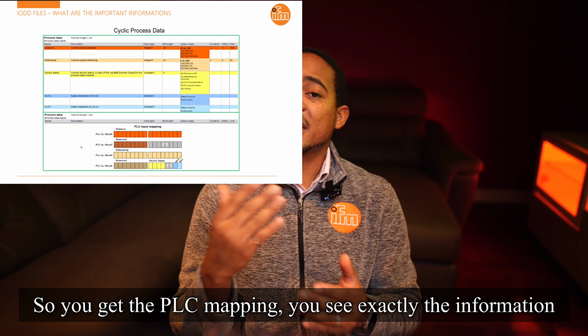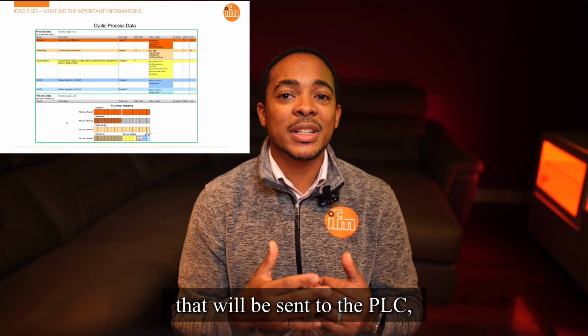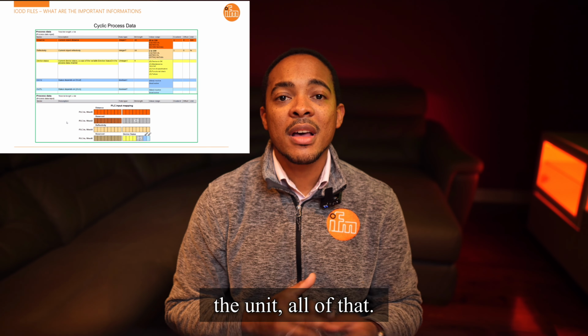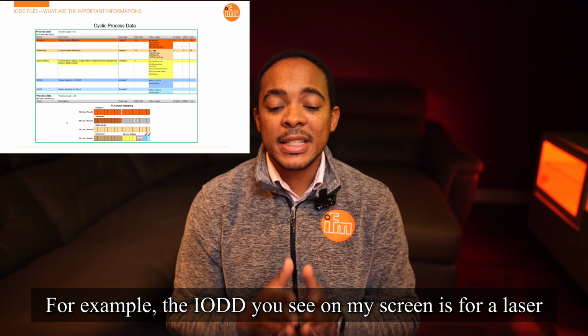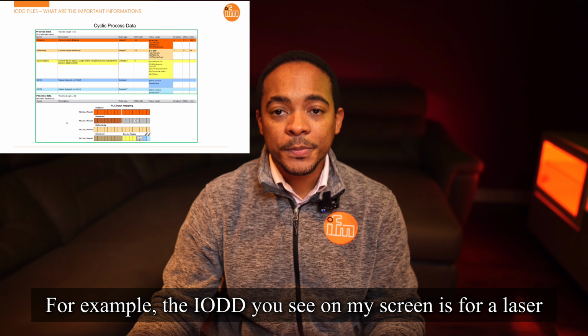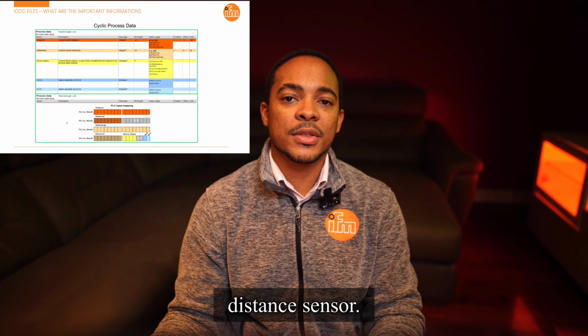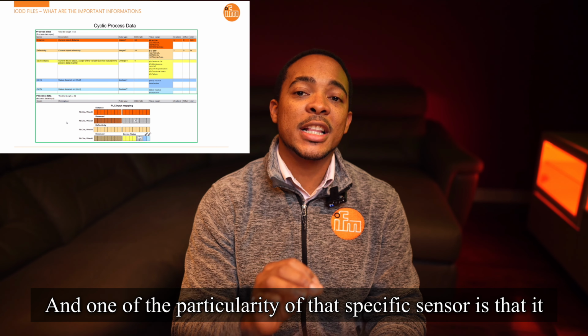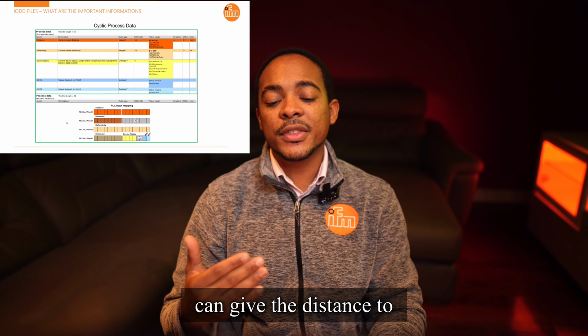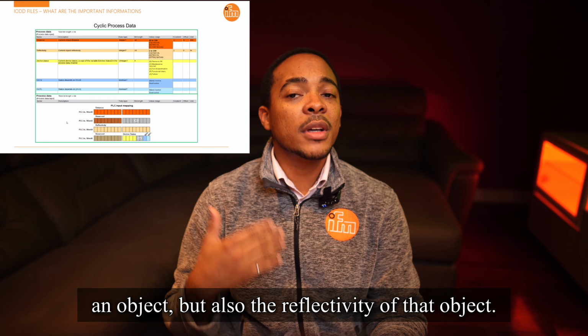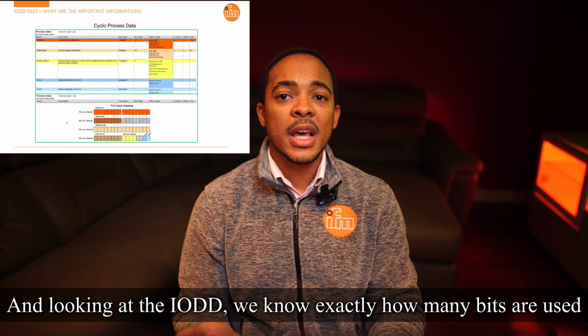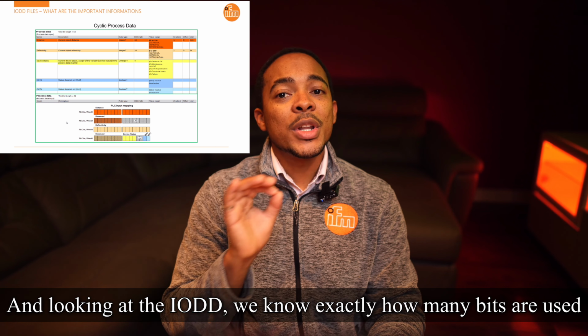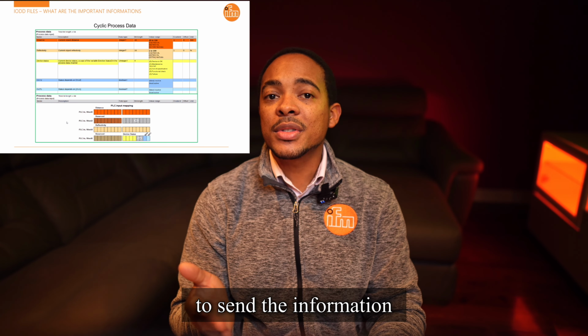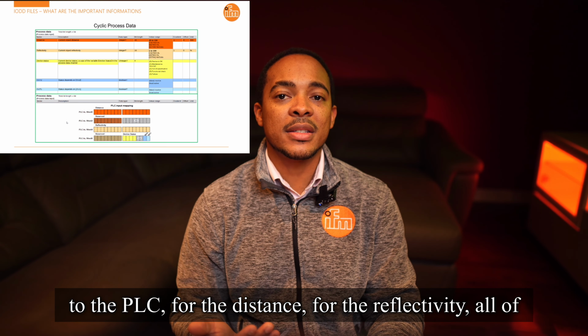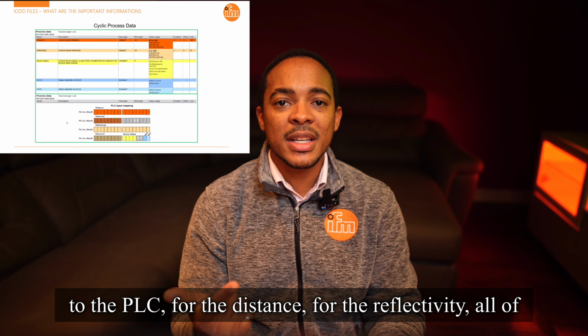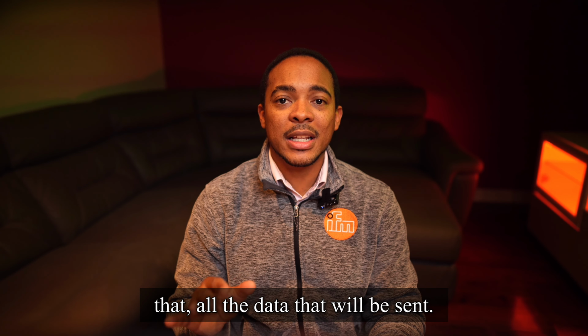So you get the PLC mapping, you see exactly the information that will be sent to the PLC, the unit, all of that. For example, the IODD you see on my screen is for a laser distance sensor. And one of the particularities of that specific sensor is that it can give the distance to an object, but also the reflectivity of that object. And looking at the IODD, we know exactly how many bits are used to send the information to the PLC for the distance, for the reflectivity, all of that, all the data that will be sent.